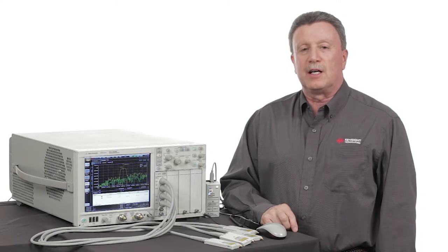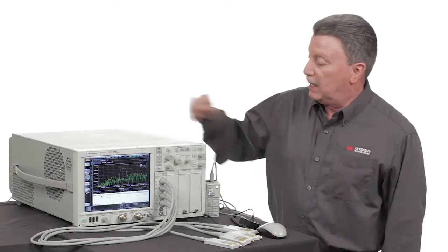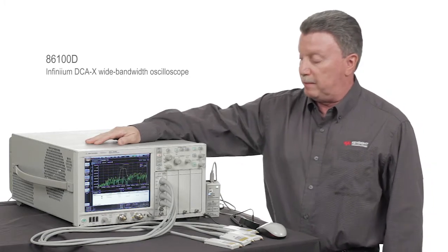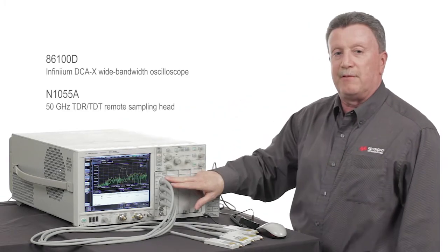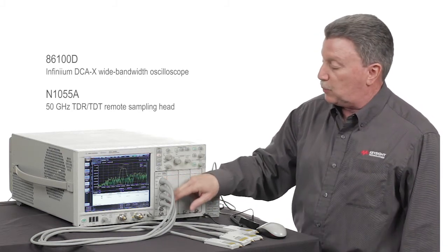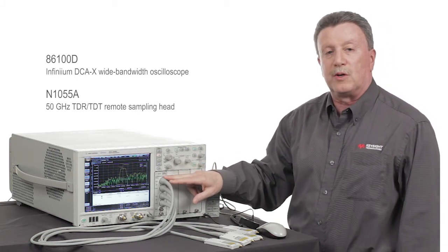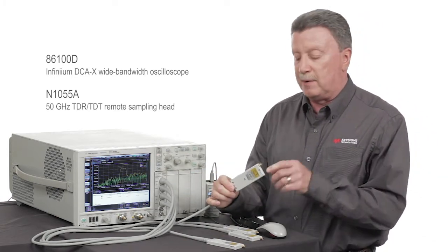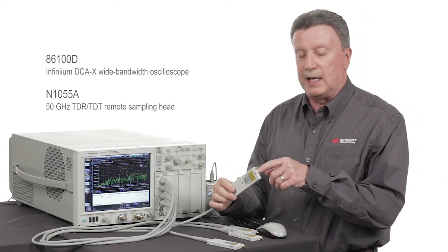Let's take a close look at the instrumentation we're going to be using to make measurements today. This is the Keysight 86100D DCA-X mainframe. And this is the N1055A 50 GHz TDR-TDT module. This one happens to have four channels, but you can also get them with two channels. And each channel has a remote head like this one with a 1.85 millimeter connector at the end.